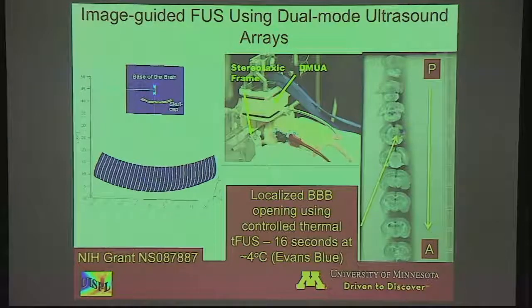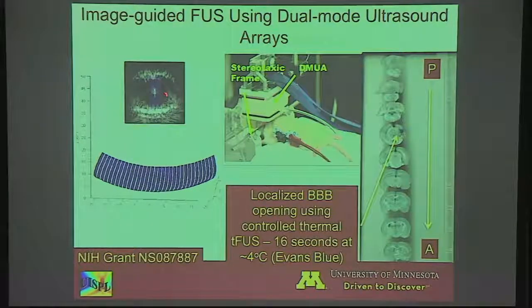Our imaging allows us to image. The quality of the imaging here is not that great, but it's enough to show me the skull, and the beam will be something like this. This is actually a realistic size at 3.5 megahertz. This beam is about 500 micron wide by less than 2 millimeter in the axial direction. So it's smaller than a sesame seed.